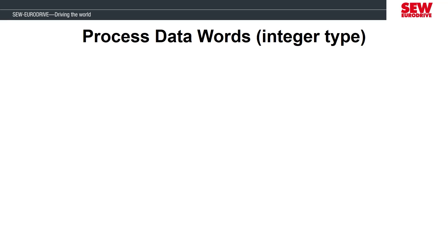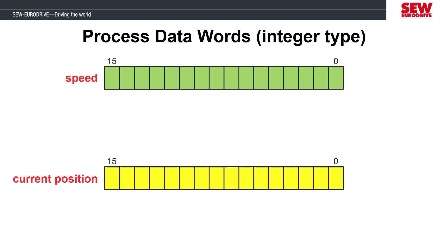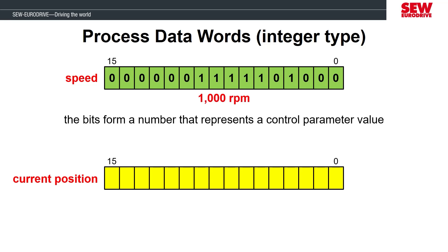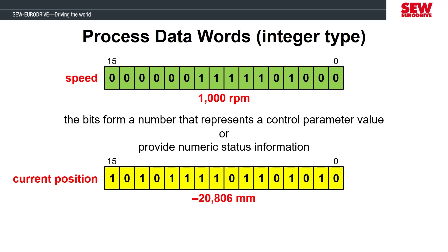The next type of process data words are integer types. These are common for the speed set point and current position feedback. For example, the speed set point is usually sent as a whole number over the process data, and the unit is commonly RPM, millimeters per second, or some other preferred unit. The binary conversion of 1000 RPM uses all 16 bits to represent a whole number rather than separate functions. These integer type words can also hold the current position as a positive or negative value — for example, a millimeter position, though it could be a different unit as well.